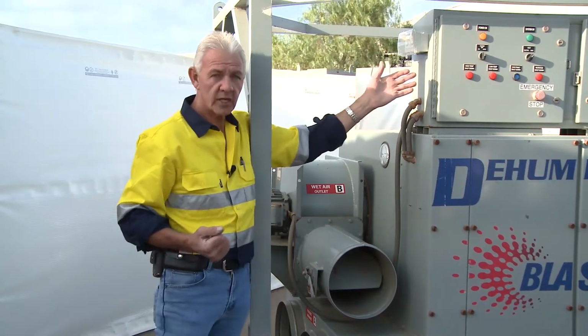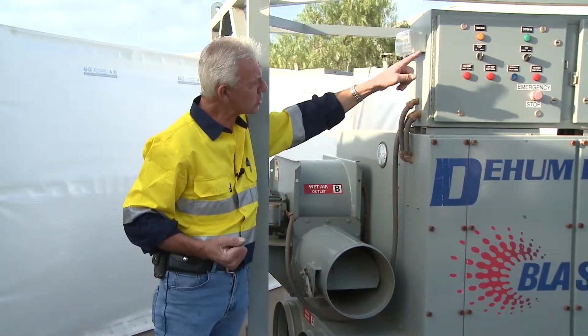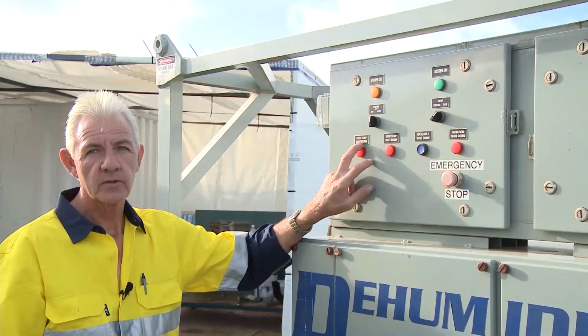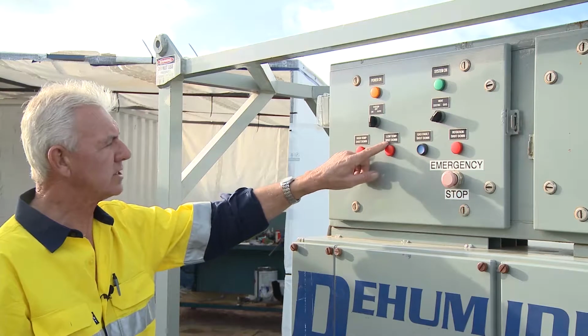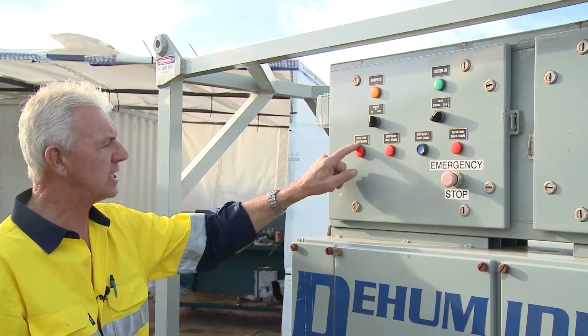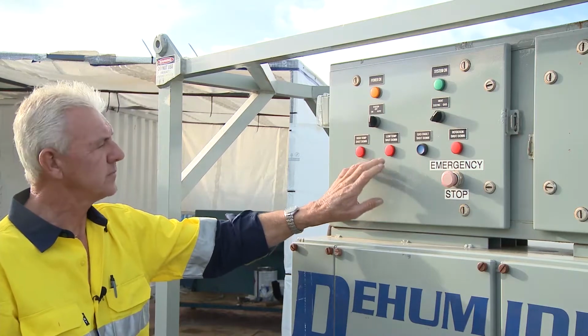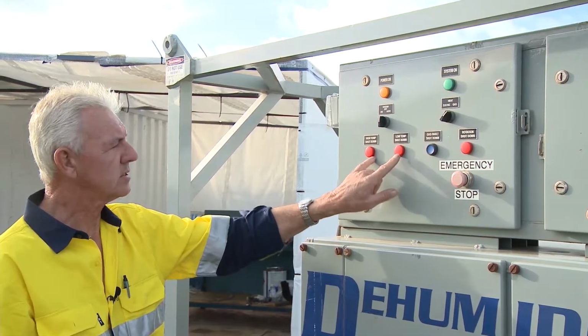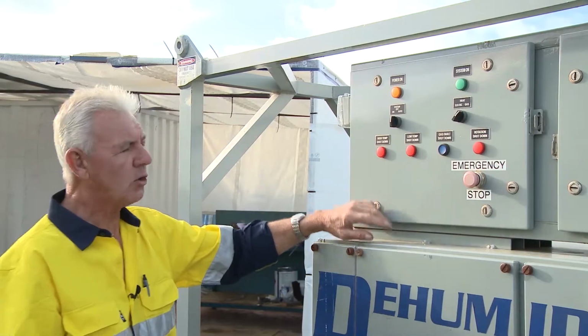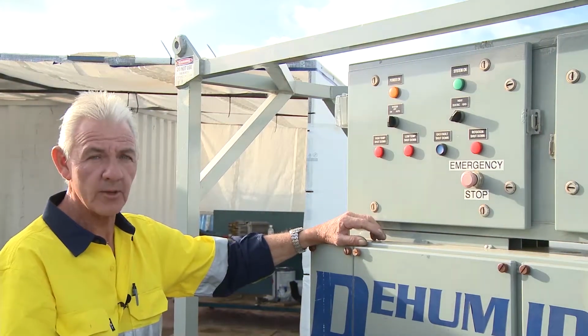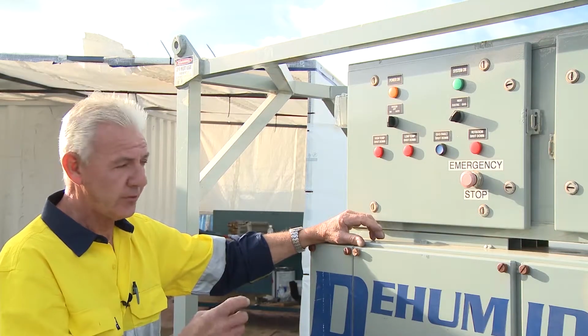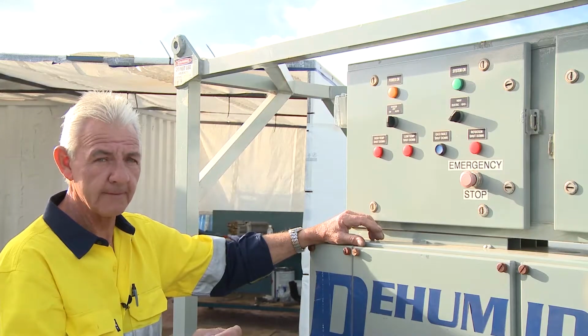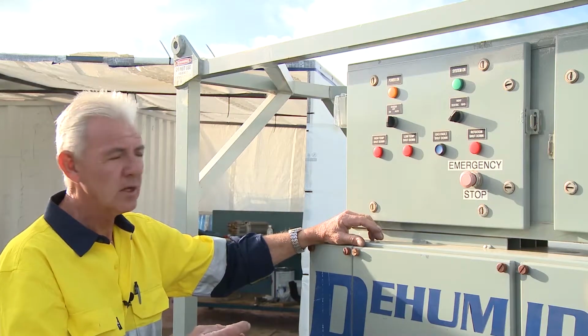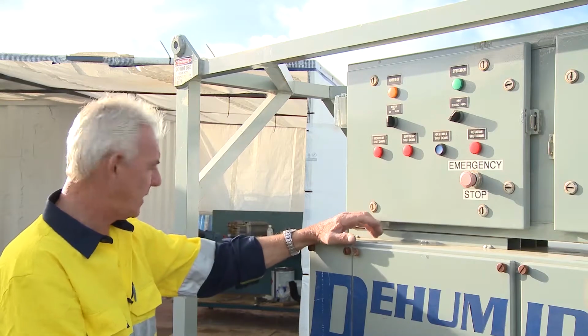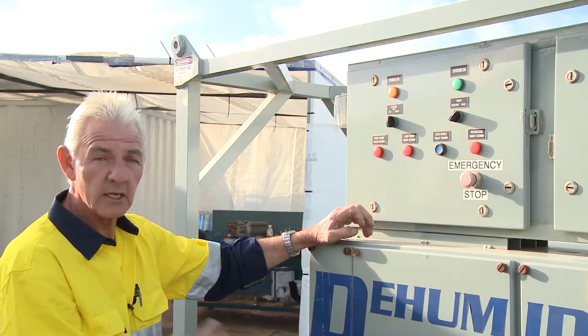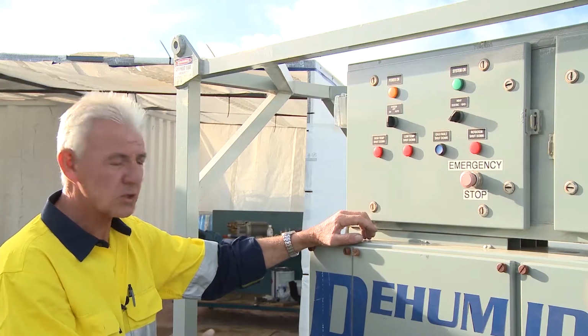So you can see here the control board itself is relatively simple because it's all labelled in relation to what I'm doing. So the labelling on this particular machine is relatively simple as far as low temp shutdown, high temp shutdown. What that means to you is when this particular section is illuminated, low or high, all it's telling us is that we've exceeded the temperature parameters within the cabinet itself, and thermostatically it's picked up that we've had a temperature spike. Is it a common occurrence? No. The only time you'll have high temp shutdown is if our filtration's blocked or the machine's struggling to pull the air through, and primarily that is the cause.